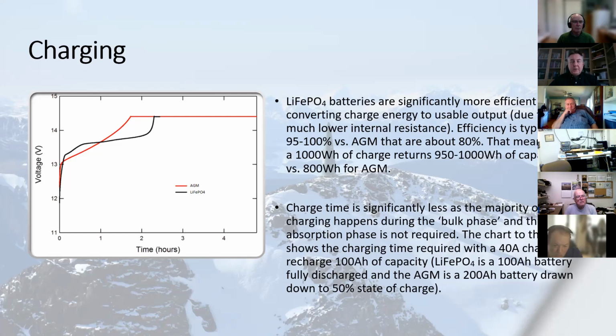Whereas the lithium iron phosphate takes a little longer to get to that full rated capacity, but essentially the moment it reaches that voltage level, it's full and you can stop charging. So the amount of time required at 40 amps of charge is 2.5 hours versus 5 hours for the AGM.